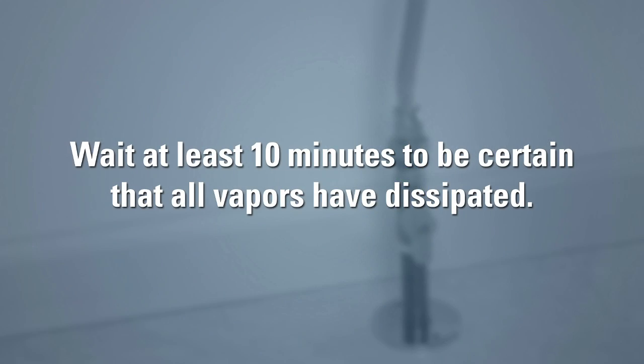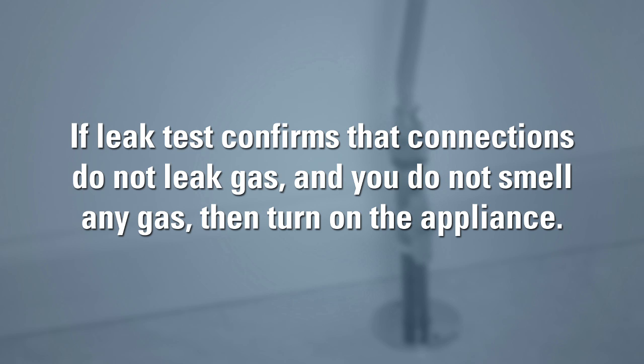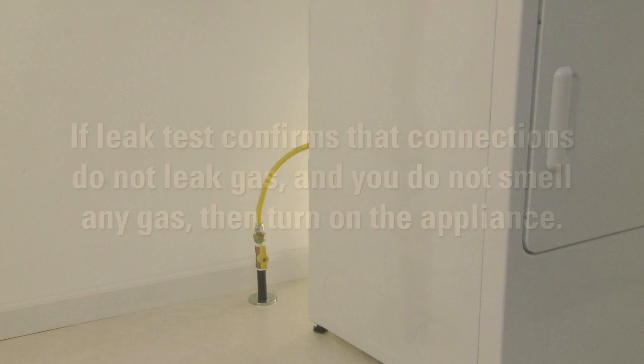Wait at least 10 minutes to be certain that all vapors have dissipated. If leak test confirms that connections do not leak gas and you do not smell any gas, then turn on the appliance. The installation is now complete.